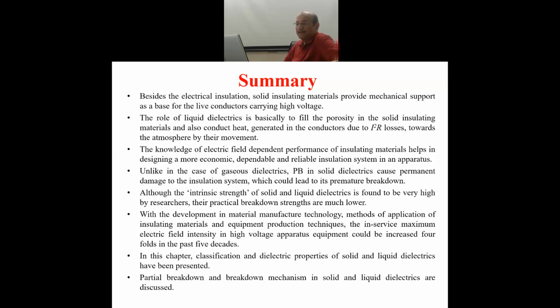And unlike in the case of gaseous dielectrics, partial breakdown in solid dielectrics causes permanent damage to the insulation system, which could lead to permanent premature breakdown. When there is a permanent damage, conducting path, treeing process, it may lead to premature breakdown and the gadget may get totally spoiled. It will cause a permanent damage to the apparatus.